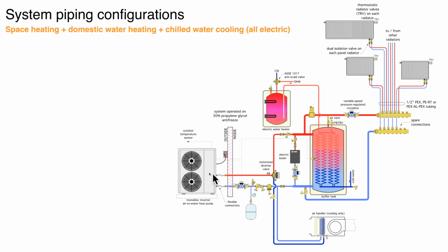Here's a system, a monoblock heat pump, three-way valve. We're going to a reverse indirect, or we're going to a cooling coil. We're using this for preheating domestic water. I'm showing a small tank type water heater as a booster. Variable speed, pressure regulated circulator going out to a manifold. And again, multiple zones of, in this case, panel radiators.